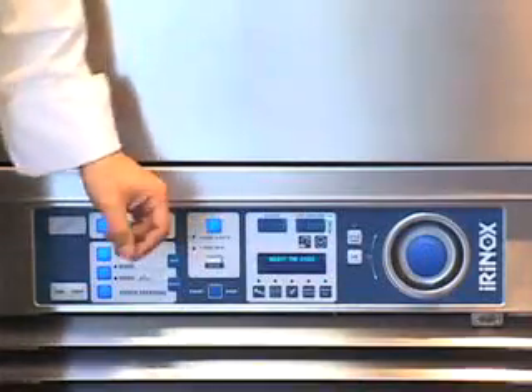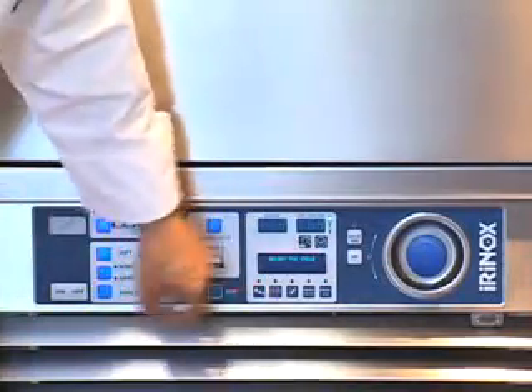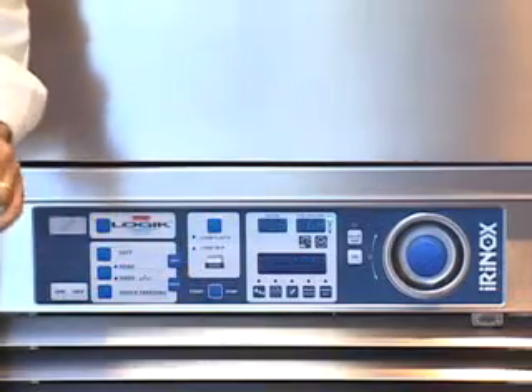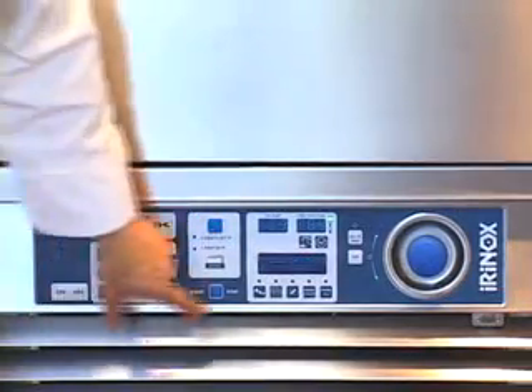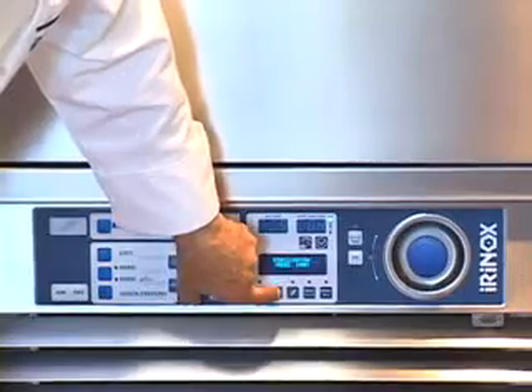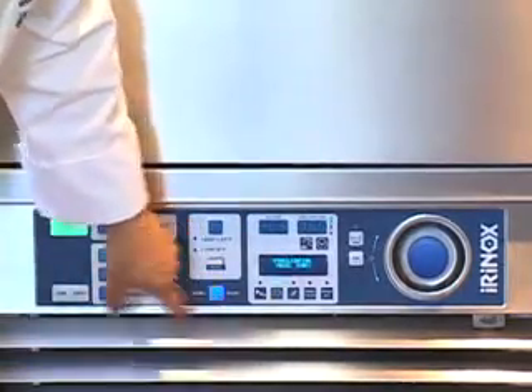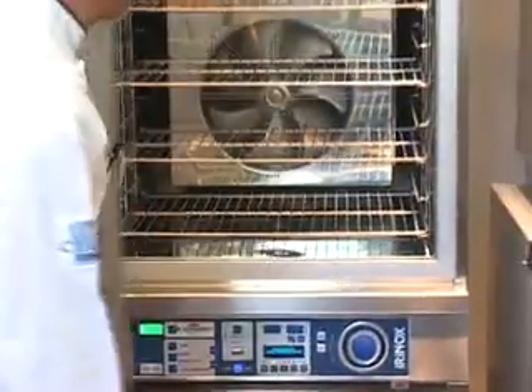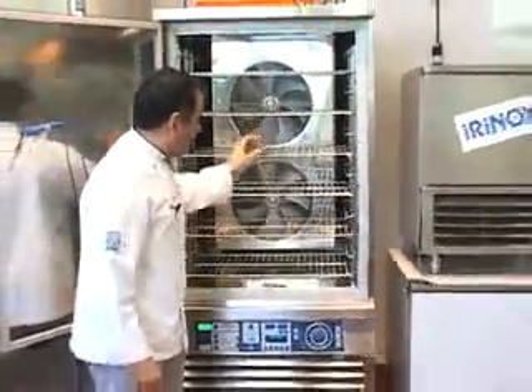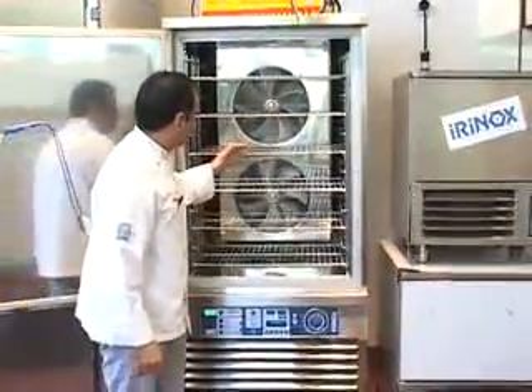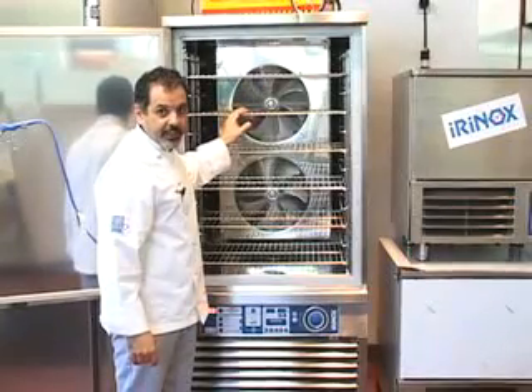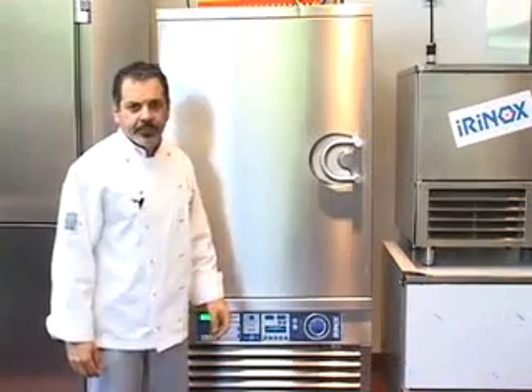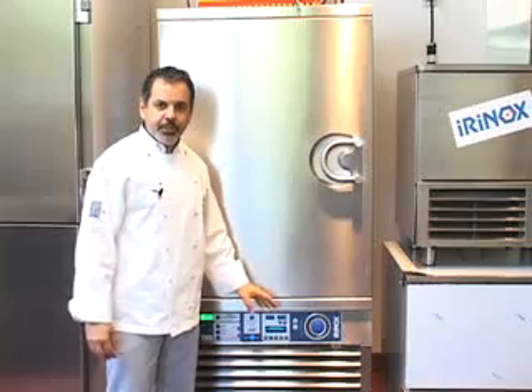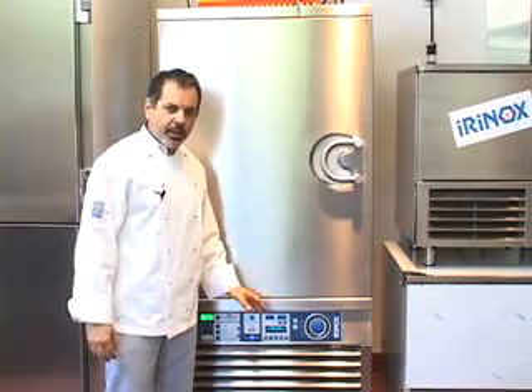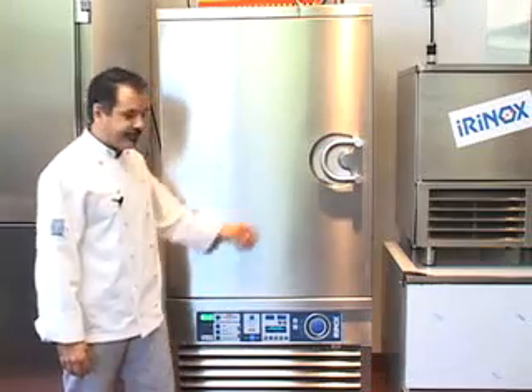I'm now going to demonstrate the UV sterilization system. When the unit has finished a cycle and is in the standby mode, I select the sterilization button and I hit the start button. For demonstration purposes, we're allowing you to see the light, but normally the light would not stay on and it will go off within 5 seconds. The sterilization cycle is 30 minutes. At the end of 30 minutes, the unit will automatically shut off from the UV cycle and is now ready to be operated.